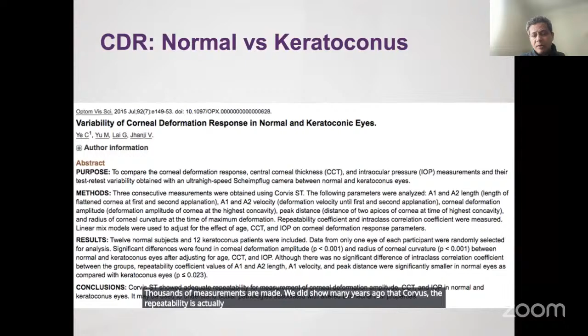We did show many years ago that the Corvis repeatability is actually quite good in normal as well as in keratoconus eyes. The newer generation Corvis has two important indices built in. One of them is the CBI, or Corvis Biomechanical Index. This is derived, although we don't need to go into details, from inbuilt software which uses a random forest AI, utilizing the deformation amplitude ratio, which means when you throw a puff of air, you have to measure how much deformation amplitude actually happens when the cornea is indented. It also uses a stiffness parameter, which is basically a separate presentation. So CBI is now inbuilt into Corvis. Basically, if you have a CBI of more than 0.5, that cornea is labeled as suspicious.